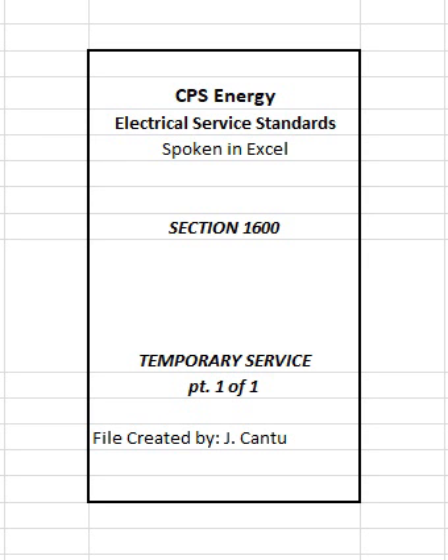Before CPS Energy energizes the temporary service, customer must satisfy permitting requirements with the authority having jurisdiction, AHJ, and the AHJ must release these permits. The street address must be legibly and permanently marked or attached on the temporary structure, but not on the meter socket cover. Temporary structures shall not be moved while energized. Note: CPS Energy will not supply electric service to any meter loop located on or attached to portable type structures or buildings. Refer to definition of portable.